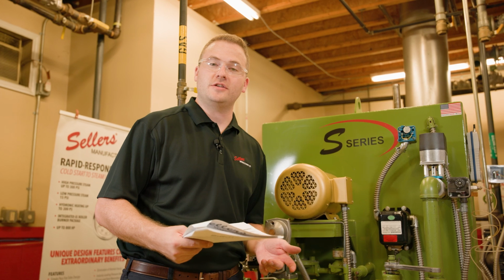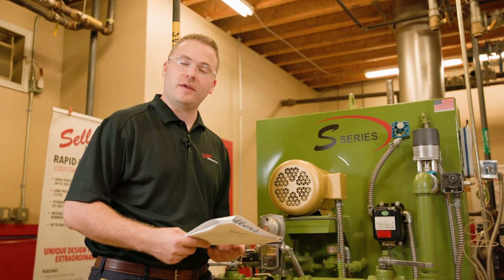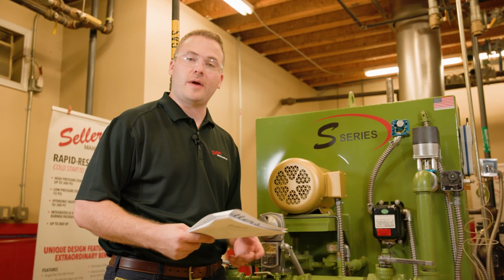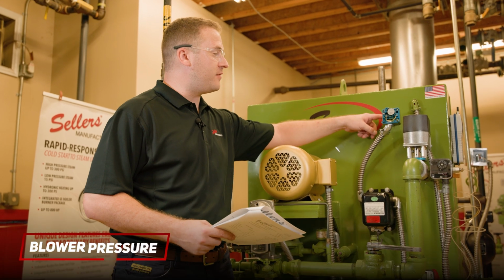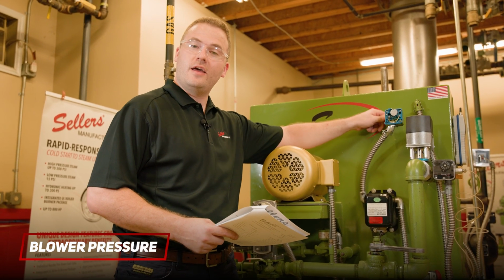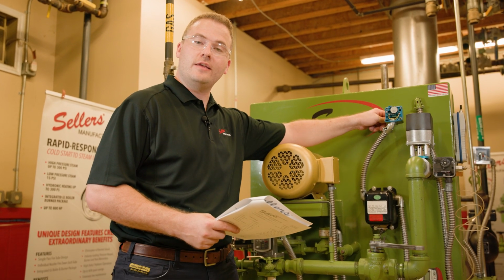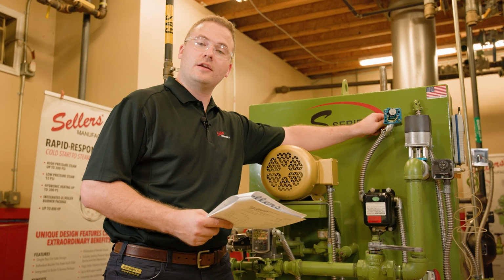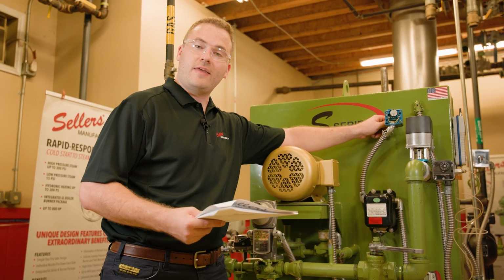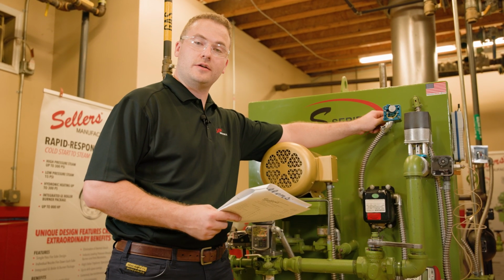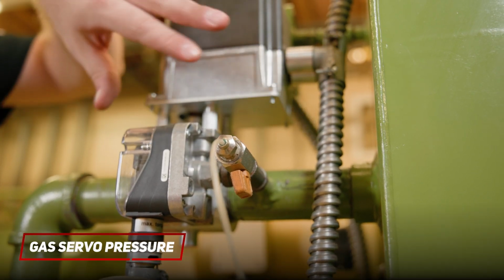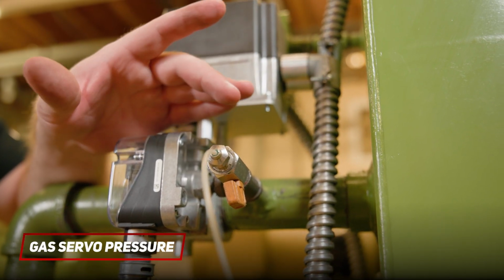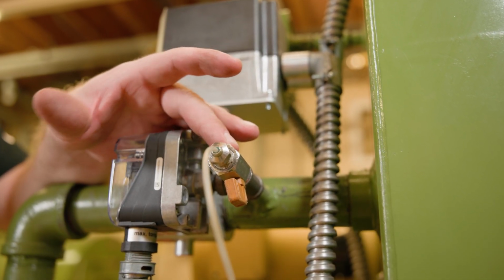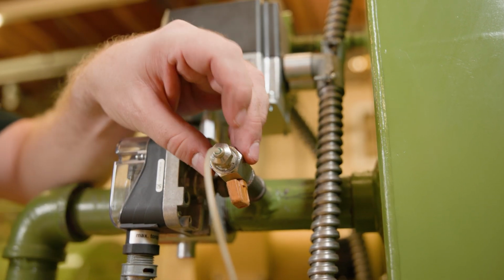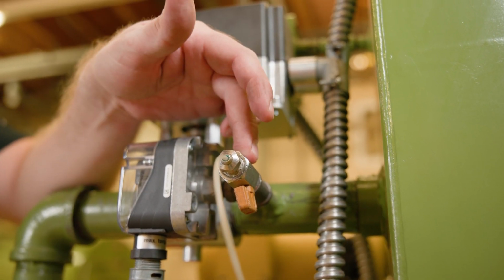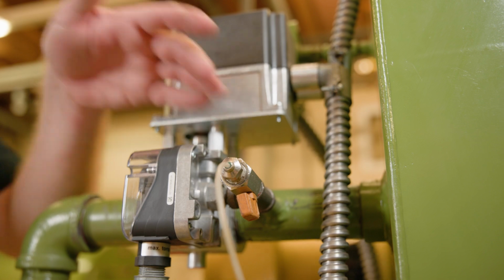Next, we're going to measure pressures for each test point. We have a couple different pressures, so let me show you how to measure them. Here behind this air switch, we have a T and a 1/4 inch plug. This 1/4 inch plug, you're going to insert a fitting and connect your manometer to it, and that is how you're going to get your blower pressure. Here on the downstream side of the gas servo valve, we have a fitting installed on this one. This is a field fitting. You're only going to have a plug, so you're going to remove the plug, and this fitting is going to be the gas servo pressure.